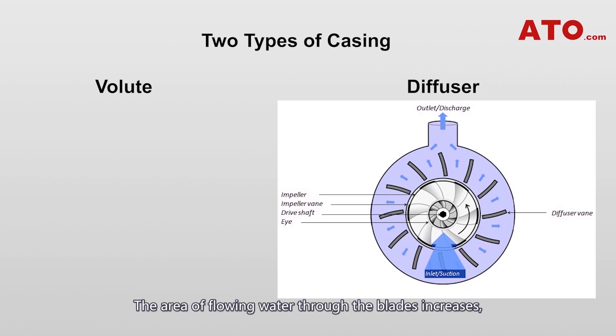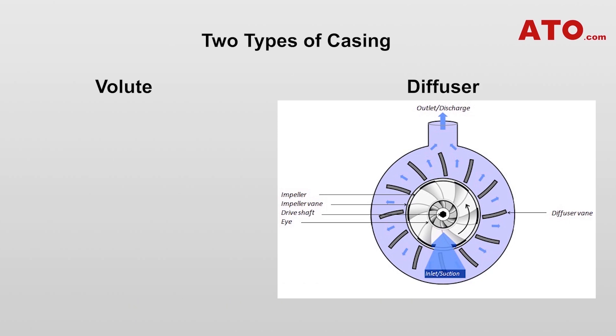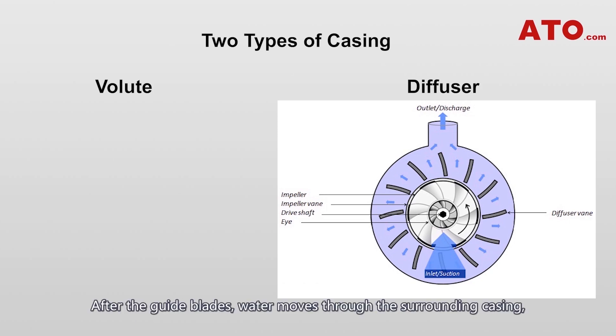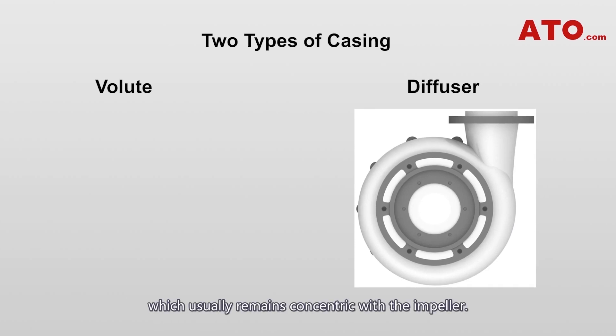The area of flowing water through the blades increases, decreasing the fluid velocity and increasing its pressure. After the guide blades, water moves through the surrounding casing, which usually remains concentric with the impeller.